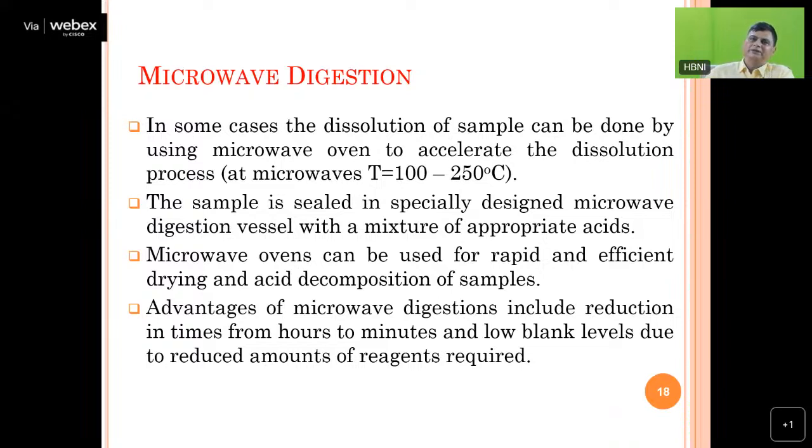Because we can vary the pressure. Once you can vary the pressure, you can cook, because instead of 1 atmospheric pressure, we can institute 10 bar or 20 bar. And then it will give us the freedom to increase the temperature not from 100 degrees centigrade, but up to 250 degrees centigrade. So the microwave digestion system can be programmed for a proper pressure, and then a temperature gradient will be given through which it will be elevated up to 250 degrees centigrade.